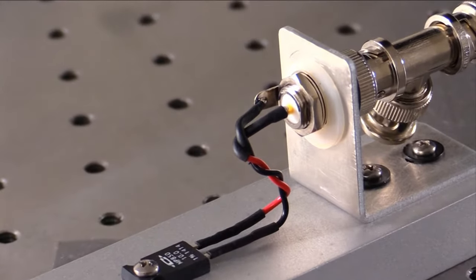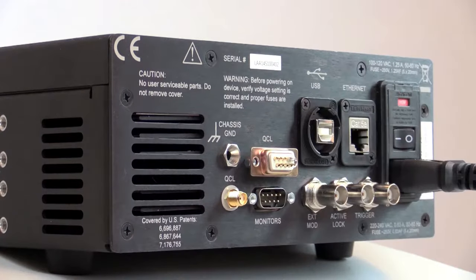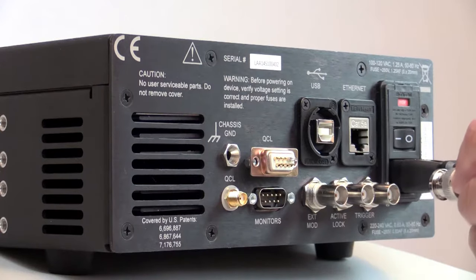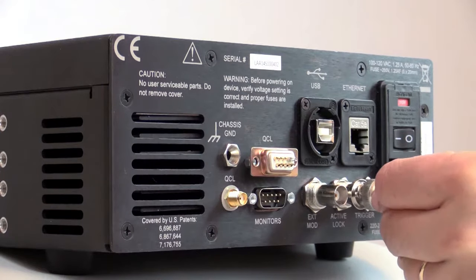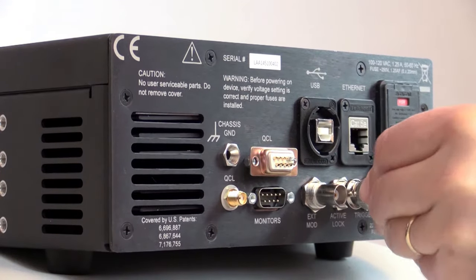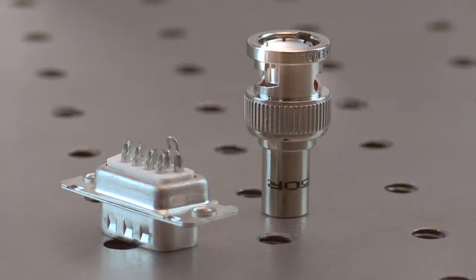For the unit to operate, pins 1 and 2 on the QCL D-sub passive interlock must be shorted, and a BNC terminator must be installed on the active interlock. A 50 or 75 ohm shorting terminator will work fine. Both of these items are supplied with the instrument.